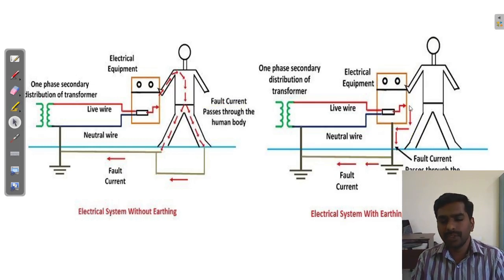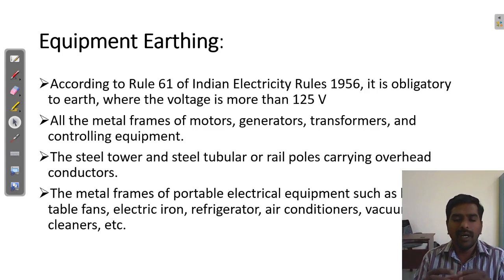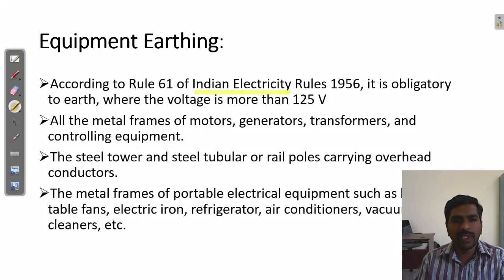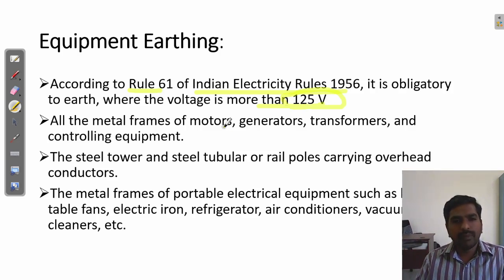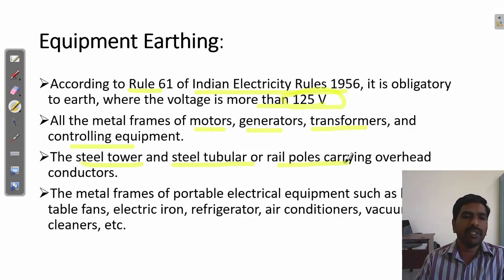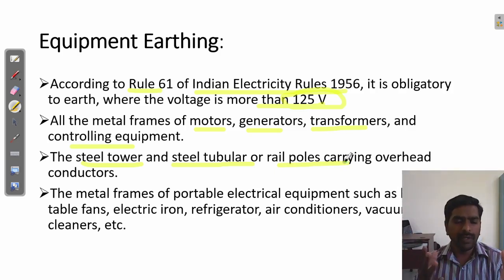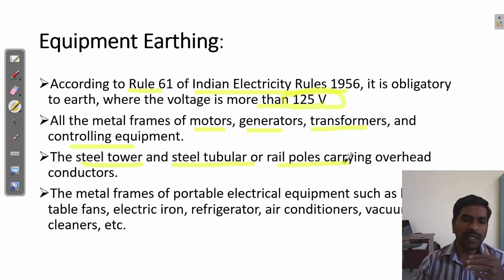If no earthing, human will get electric shock. Earthing is very important. The earthing equipment used in our home or industry is mentioned by Indian Electricity Rules 1956, Rule Number 61. It says that wherever voltage more than 125 volts is used, it should be earthed. The source, equipment, or appliances should be grounded. All metal frames of motors, generators, transformers, and controlling equipment should be grounded. Steel towers, steel tubular, or rail poles carrying overhead conductors should be grounded.